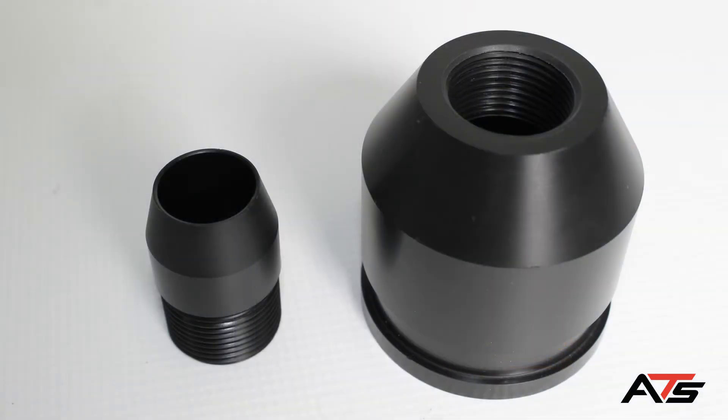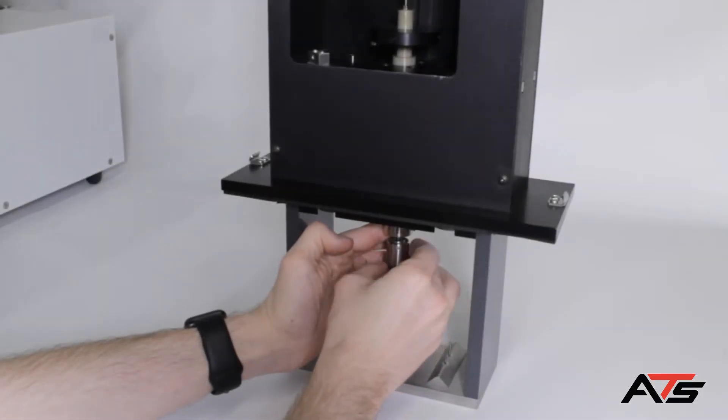Remove the foam from inside the load shroud if present and unscrew the lower portion of the load shroud from the upper portion. Lift the load nose and carefully screw it onto the threaded stud in the bottom of the load cell until it is finger tight.